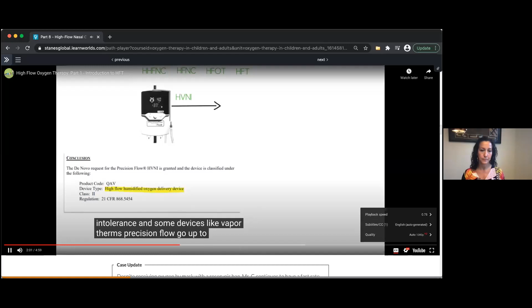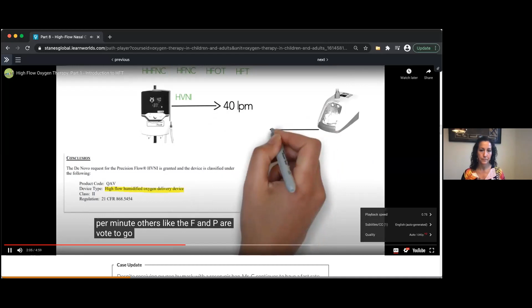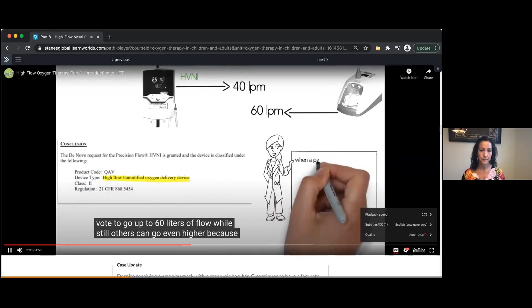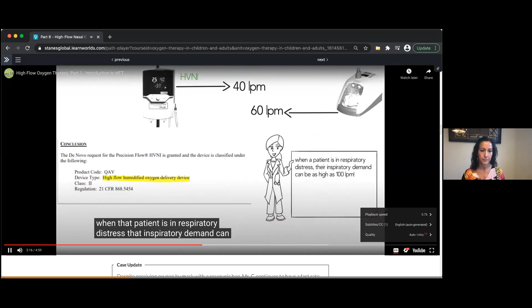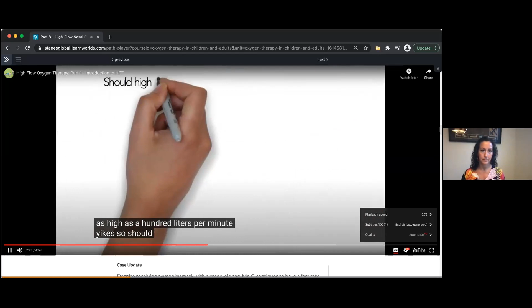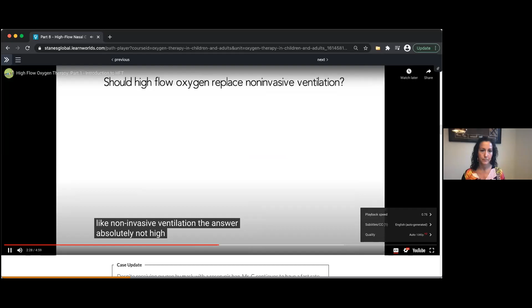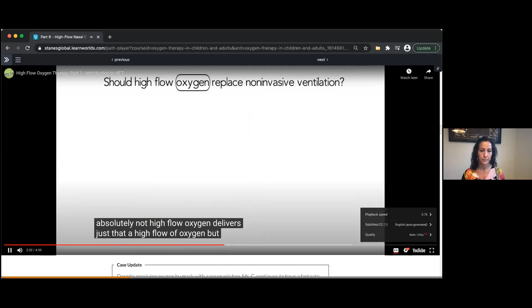And some devices, like Vapotherm's Precision Flow, go up to 40 liters per minute. Others, like the F&P Airvo 2, go up to 60 liters of flow, while still others can go even higher. Because at the end of the day, we're just trying to meet the inspiratory flow of a patient. And when that patient is in respiratory distress, that inspiratory demand can be as high as 100 liters per minute. Yikes. So should high flow therapy be a replacement to other forms of therapy like non-invasive ventilation? The answer, absolutely not. High flow oxygen delivers just that, a high flow of oxygen.